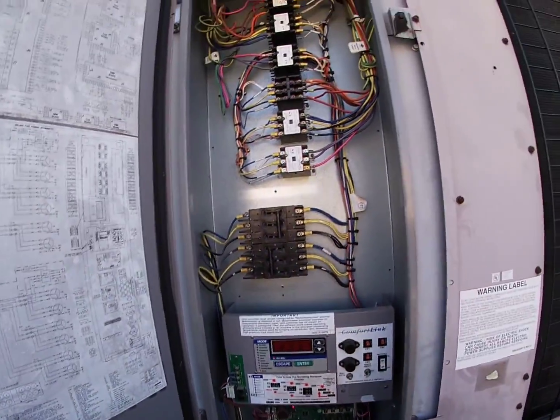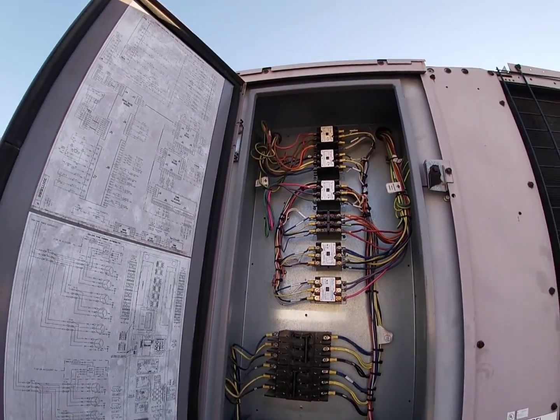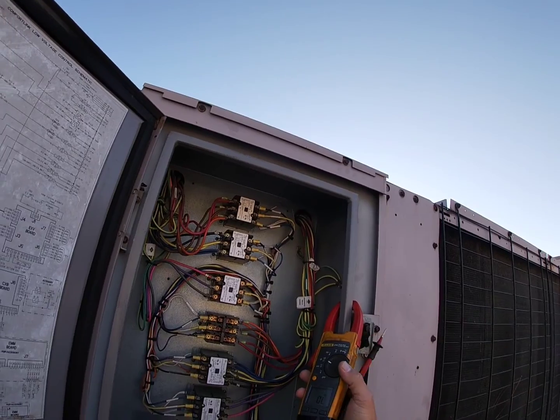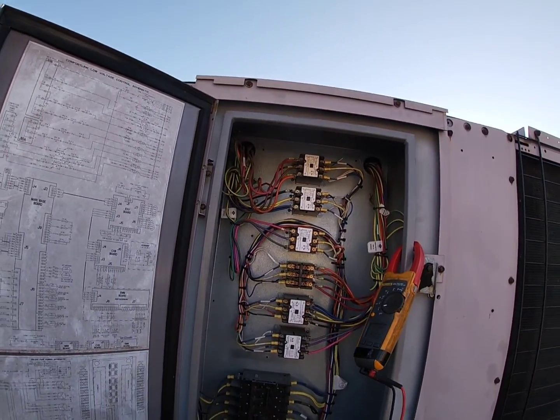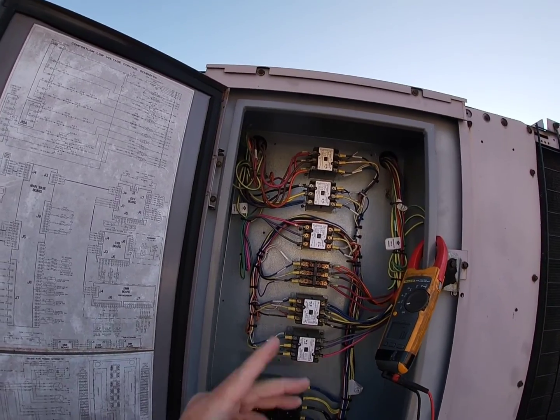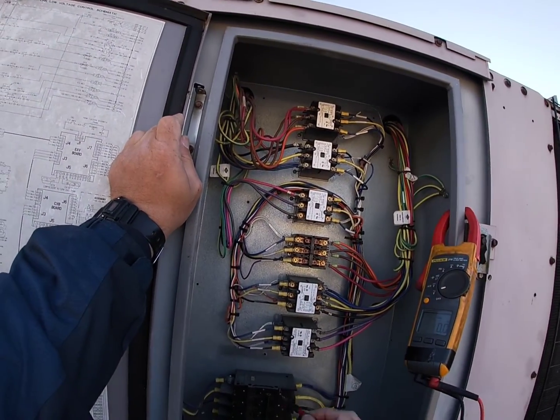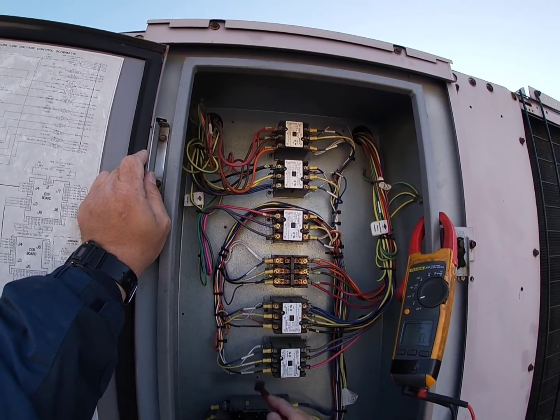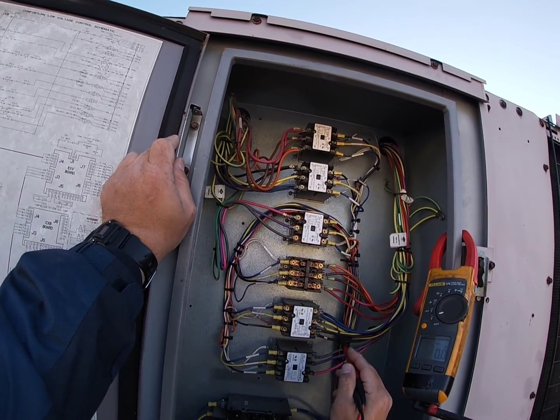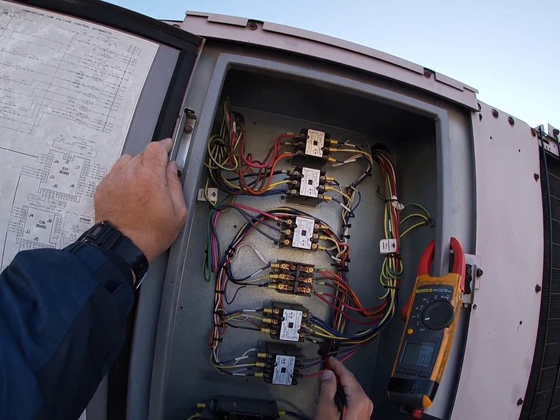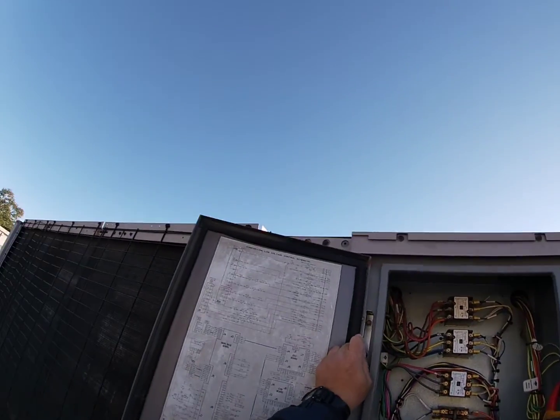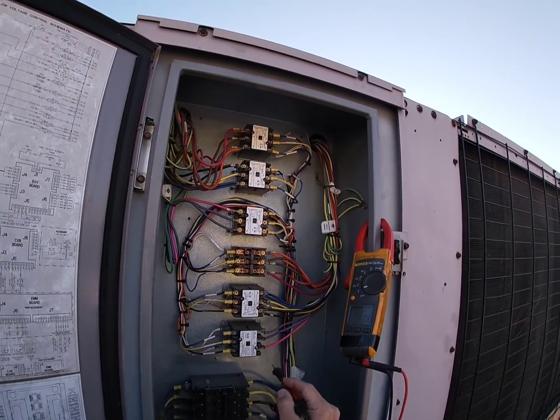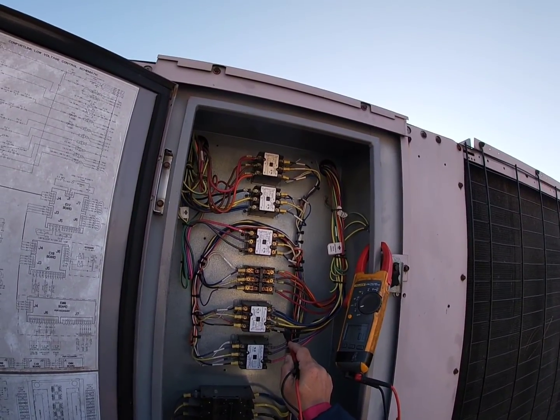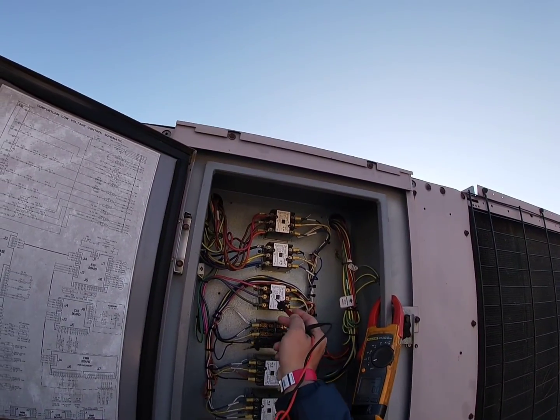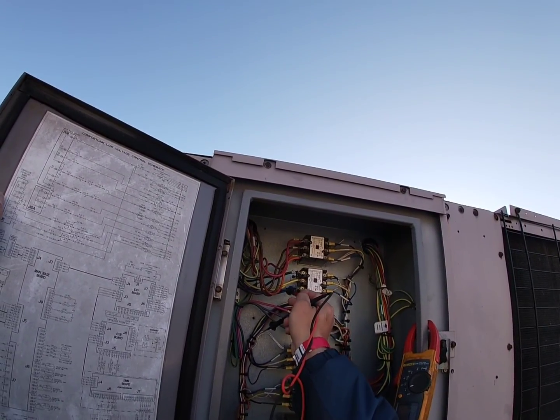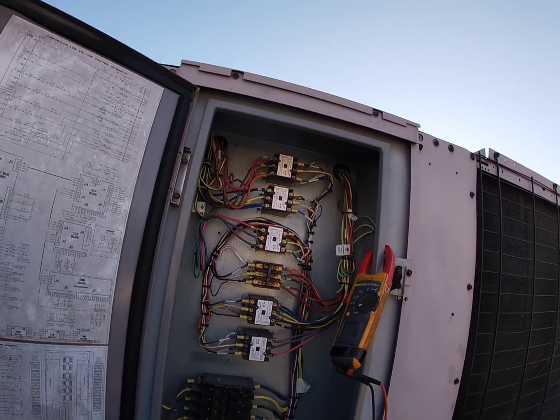So next thing we're gonna do here is we're gonna ohm out these motors here. We got my meter here, we're gonna ohm them out and see if we got anything that's tripped off here. So first we're gonna see which contactor, which ones of these condenser fan motor contactors feed off of this breaker here. So black, yellow, and blue is gonna be your power. These are going to your condenser fan motors. Same thing here, you got 2 condenser fan motors. So this chiller has 4 over here and 6, so a total of 10. So you have 1, 2, 3, 4, 5, 6, 7, 8, 9, 10. So that's your 10 condenser fan motors there.